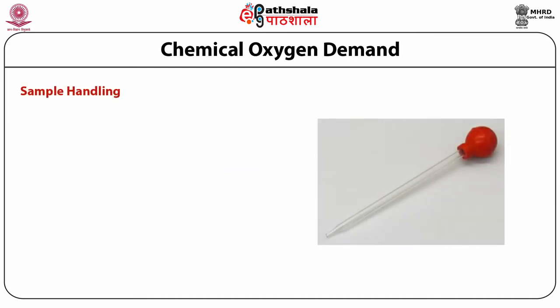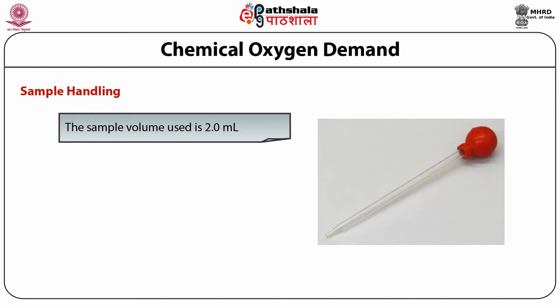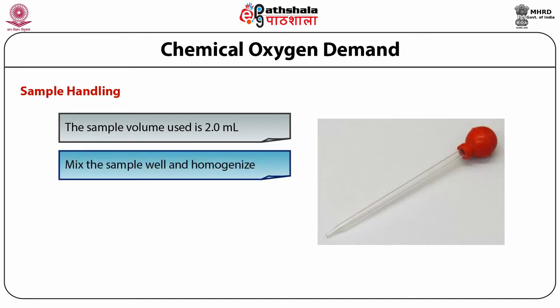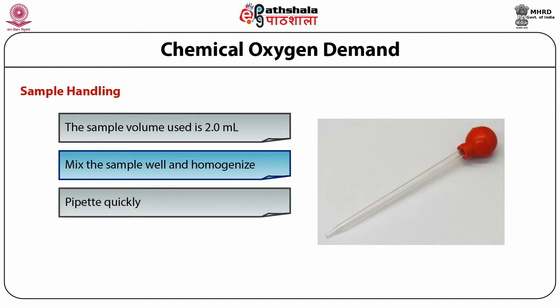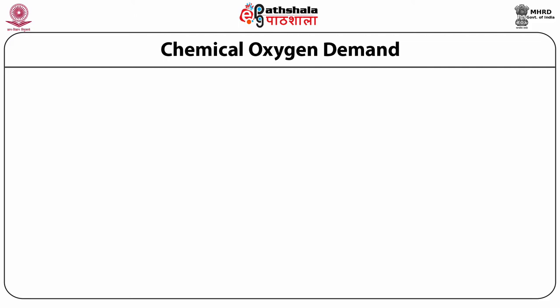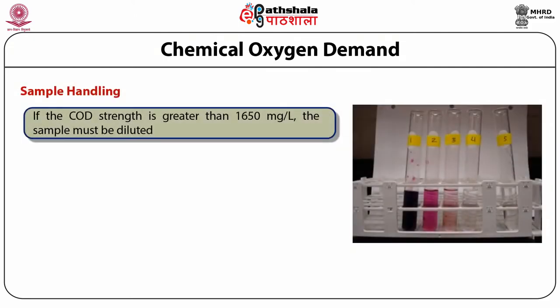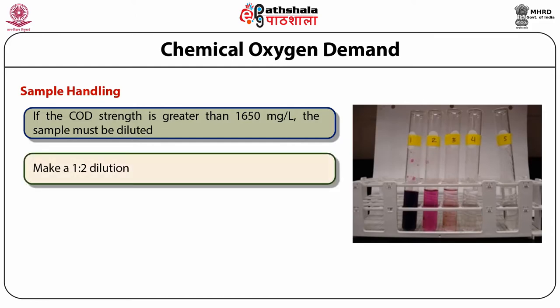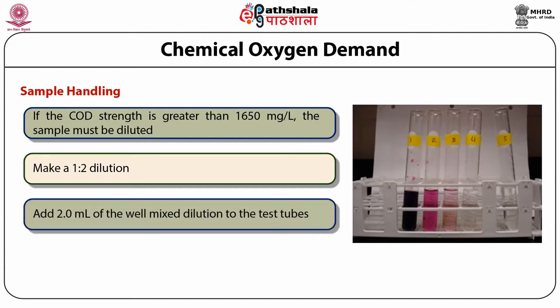For sample handling, the sample volume used for the COD test is 2 ml, so measuring the sample volume is critical. Be sure to mix the sample well and homogenize if necessary. Pipette quickly to avoid settling errors. If COD strength is greater than 1650 mg/L, the sample must be diluted — make a 1 to 2 dilution by measuring 50 ml of sample and adding to 50 ml of deionized water, then add 2 ml of the well-mixed dilution to the test tube.